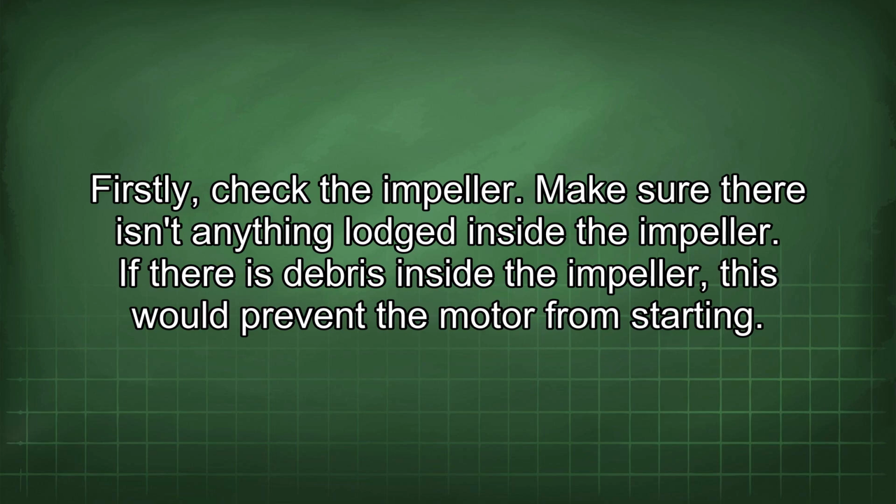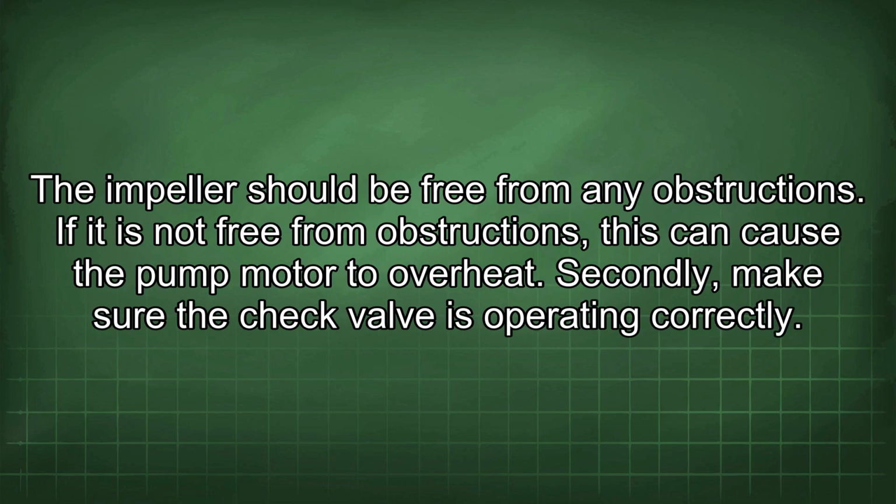Firstly, check the impeller. Make sure there isn't anything lodged inside the impeller. If there is debris inside the impeller, this would prevent the motor from starting. The impeller should be free from any obstructions. If it is not free from obstructions, this can cause the pump motor to overheat.